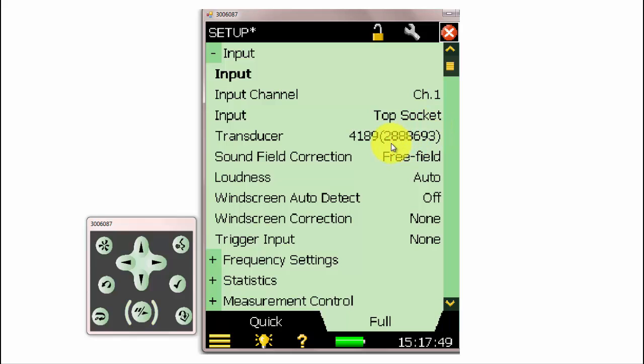When we calibrate a transducer with its serial number, a record of that calibration will be kept on the meter.